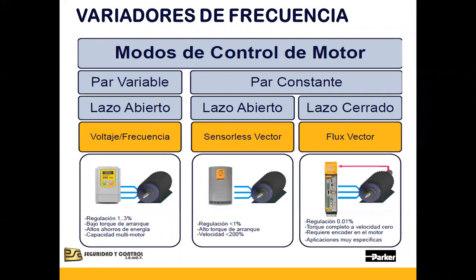El drive ofrece el torque demandado por la carga, sin compensación por la dinámica del motor. Hay arranque limitado y deficiente operación a bajas velocidades. Para el par constante en lazo abierto, Parker maneja integrada dentro del variador AC10 la función sensorless vector, que maneja una regulación menor al 1% en comparativa con la frecuencia de entrada del motor. Maneja un alto torque de arranque con velocidades de hasta 200%.